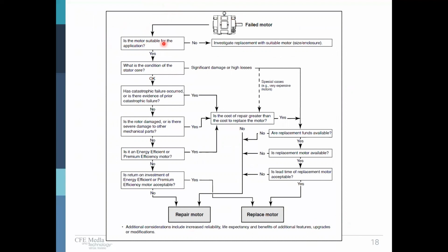If it's that drip-proof motor in a harsh environment, we're going to investigate replacement with a suitable motor in terms of size and enclosure. You need the replacement motor to fit where the old motor was. So we want to look at those things. And I'm going to jump down to this little bullet at the bottom. Additional considerations include increased reliability, life expectancy, benefits of additional features, upgrades or modifications. Those are some of the other elements that, whether we're going to repair it or replace it, we want to think about as we go.